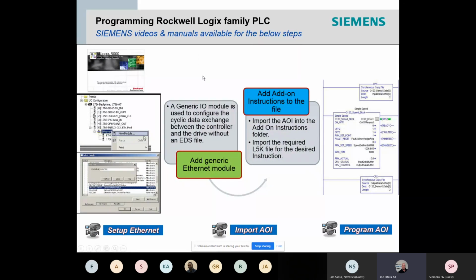There are Siemens videos and manuals available for the below configurations and steps on how to integrate the add-on instructions. We're not Rockwell experts here, but from my experience, there is an add-on block that we can simply drop in and set up the address range, and it will talk to the Siemens PLCs.